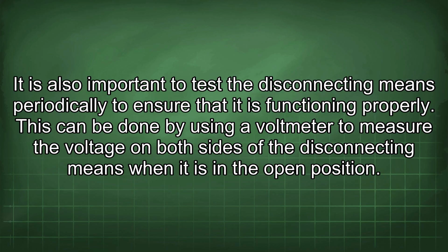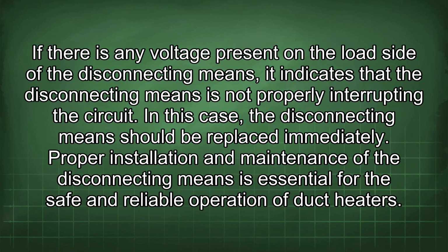This can be done by using a voltmeter to measure the voltage on both sides of the disconnecting means when it is in the open position. If there is any voltage present on the load side of the disconnecting means, it indicates that the disconnecting means is not properly interrupting the circuit. In this case, the disconnecting means should be replaced immediately. Proper installation and maintenance of the disconnecting means is essential for the safe and reliable operation of duct heaters.